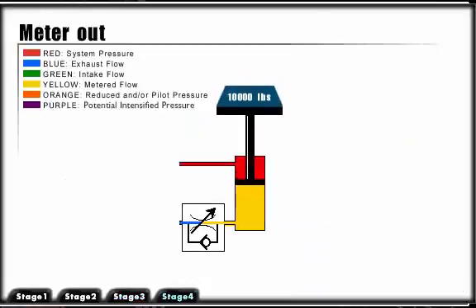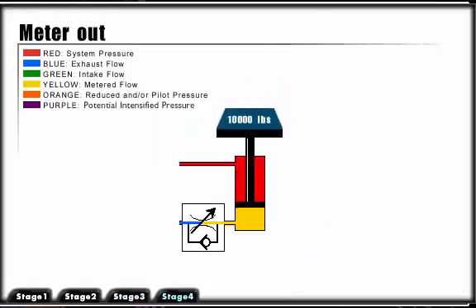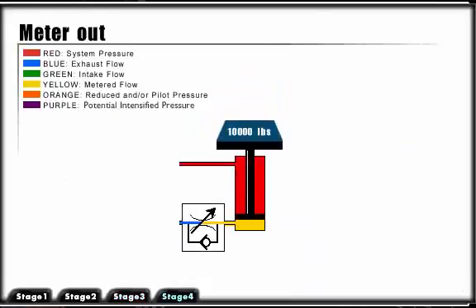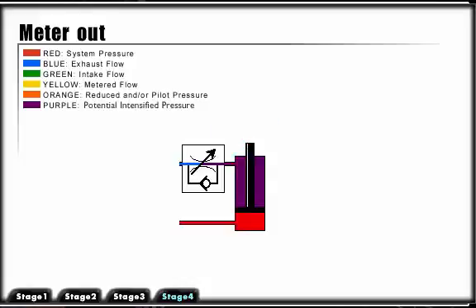An advantage of meter out is that it will prevent a cylinder from overrunning and consequently cavitating. A disadvantage to meter out can be pressure intensification. This can occur with a substantial differential area ratio between the rod and piston.